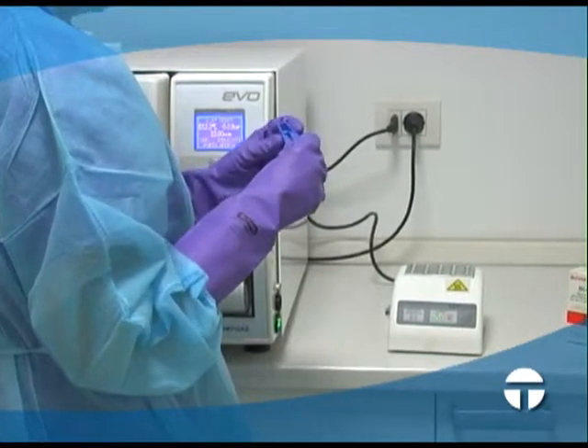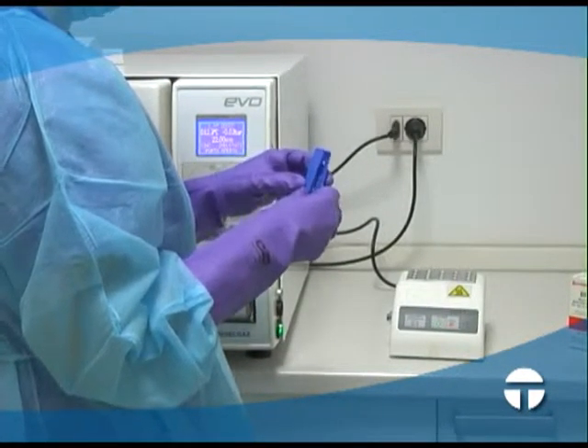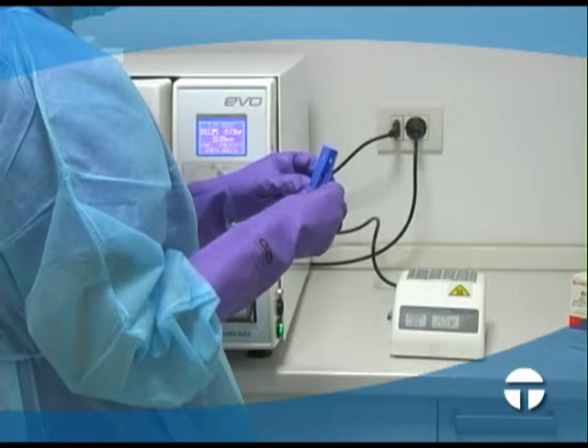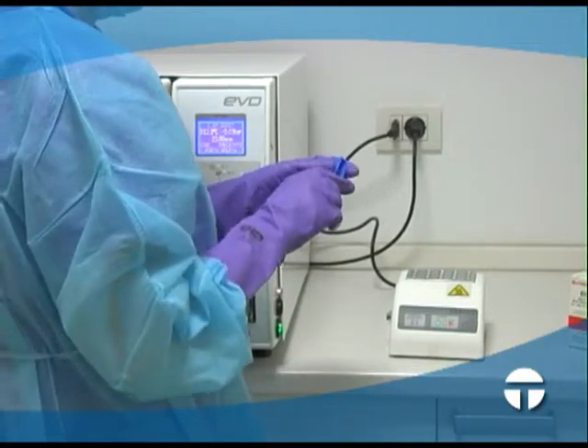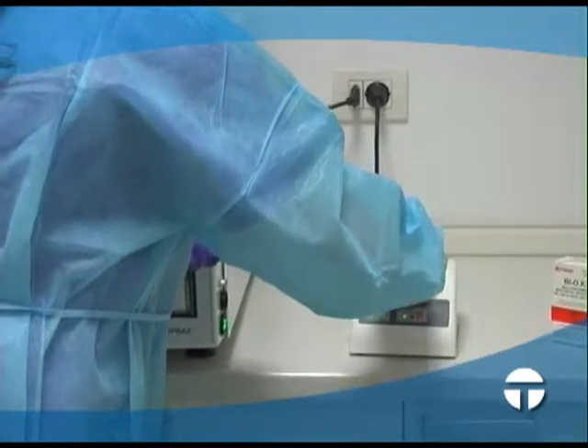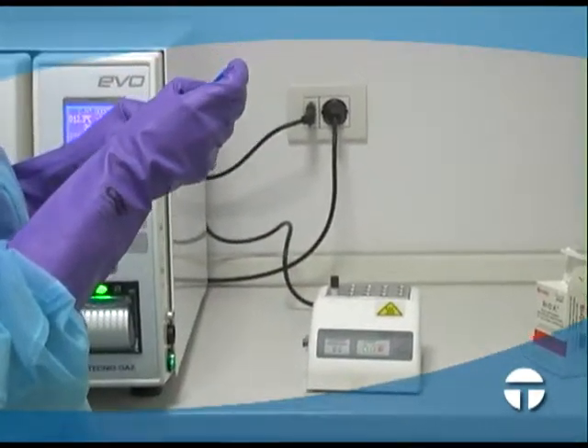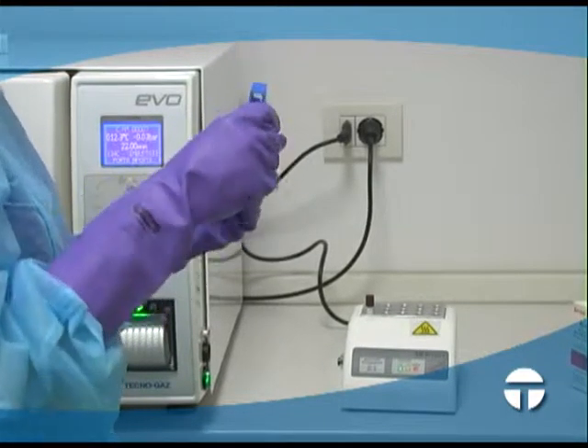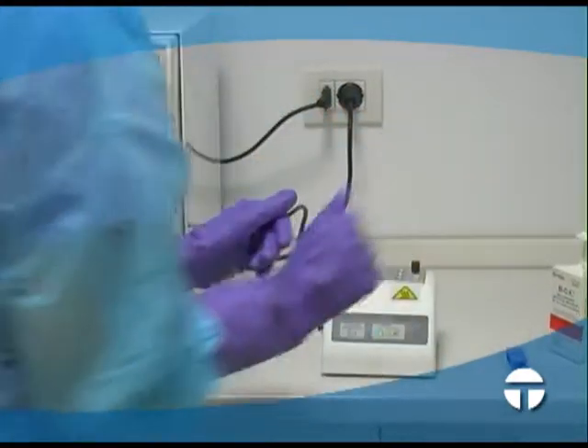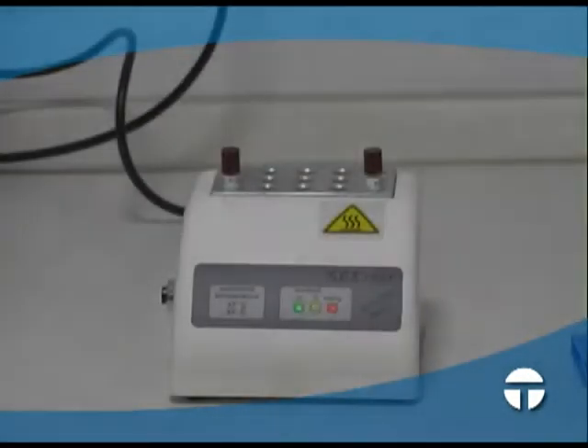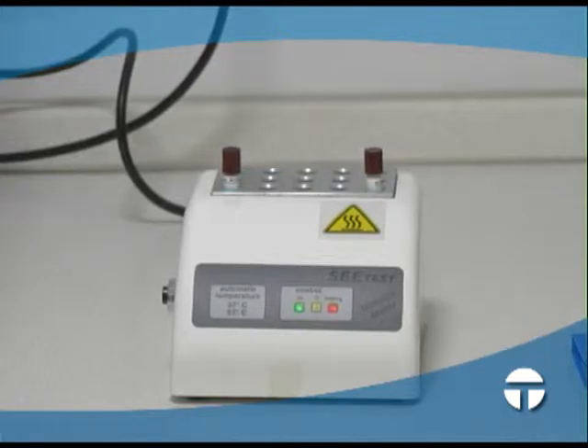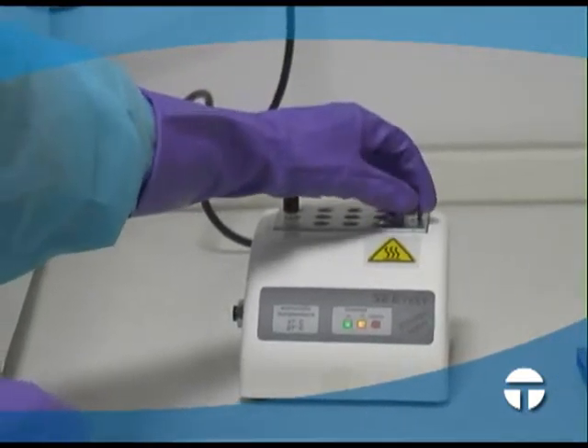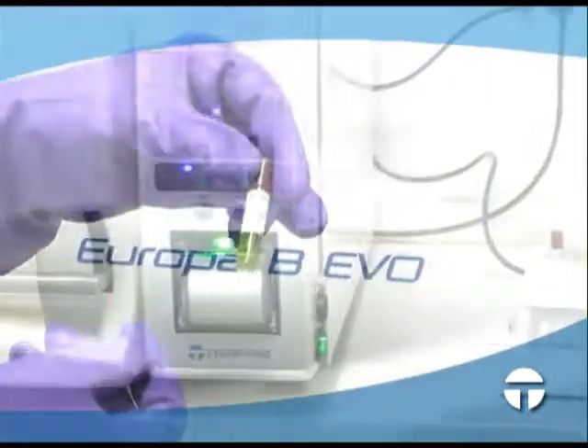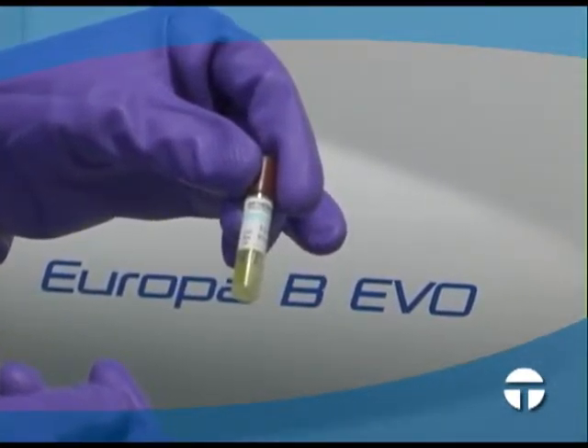Wait 1 minute, then activate it with the appropriate device and place it in the biological incubator for 48 hours, together with a non-sterilized test vial activated in the normal way. Check the result after 48 hours. The test vial will have turned yellow. The sterilized vial, if it has reacted correctly, will have retained its original color.